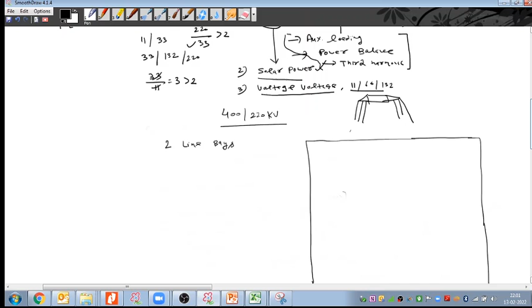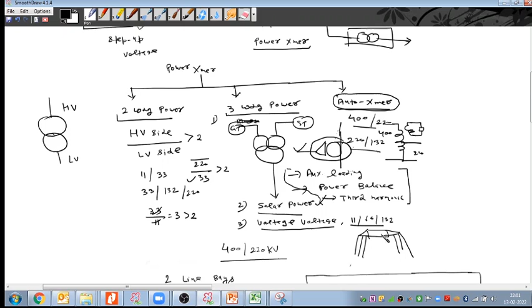Below this tower there will be some series of towers, right? From where this 400 kilovolt is coming from the sending end substation, right? So there are 2 line bays. So I'm just drawing one single line. Line bay 1 means, do not take one line. It means there is R Y B 3 phase, but all the R phase, Y phase and B phase are similar and the equipment is the same. So in place of drawing 3 lines, I'm just drawing 1 line, and I can cross like this. So this is representing the line bay. This line representing the line bay will have 3 phase.